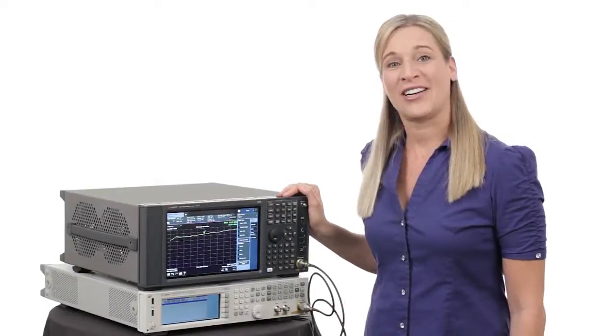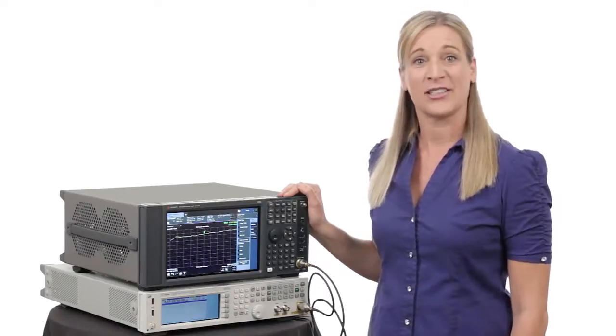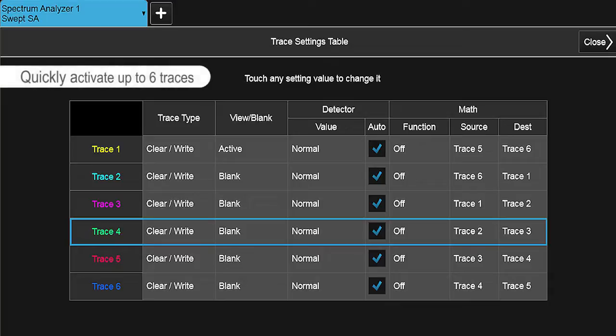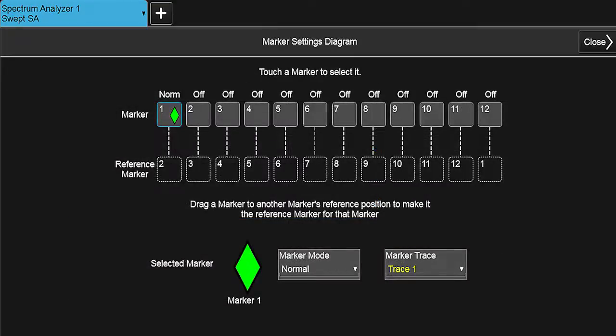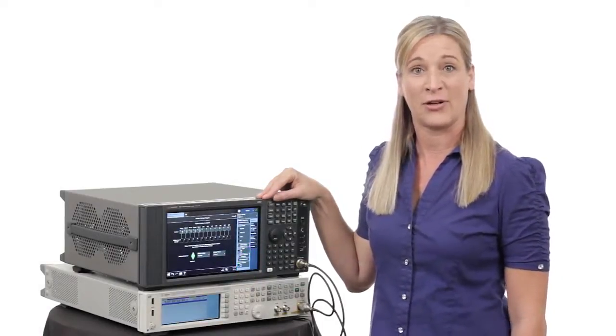So before I get started, I'd like to show you two new features that we've added to our multi-touch X-Series Analyzers. First, we've added a nice easy-to-use trace settings table. I'm able to quickly activate in this SA mode up to six traces at a time. We've also added a new marker settings diagram. I can quickly access the diagram and turn on up to 12 markers, and what I've done is I've turned on five markers and then applied them to each of the five traces that I've also turned on.